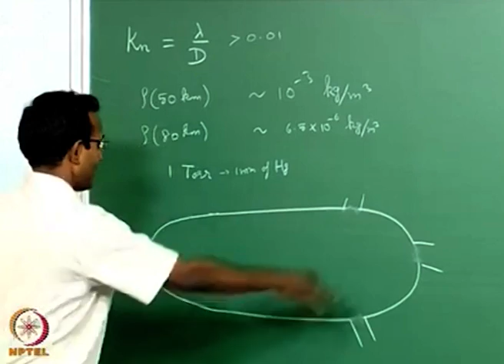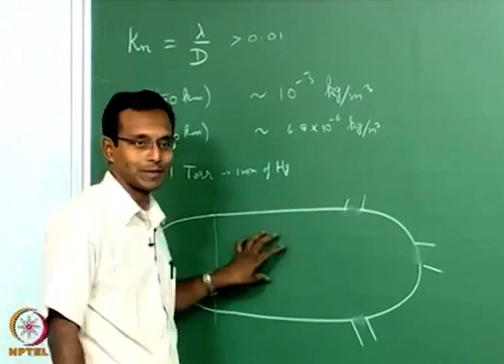Other than that, the pump should be continuously running to maintain the pressure, because there is always leak, and the pump should be removing the excess molecules that are entering due to leak. Then the pressure will be maintained. That is the idea there. And the pump should be running for that, capable of running with the required leak rate.